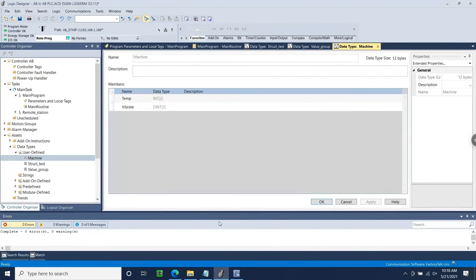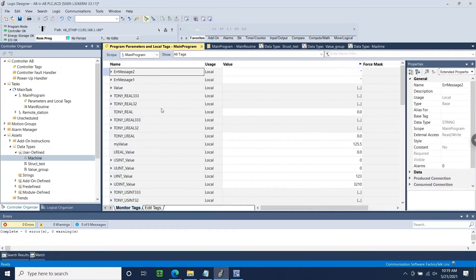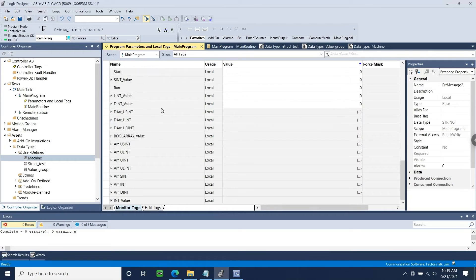Next, let's open our Compact Logix project in Studio 5000 and export our tag list. There are two different file formats that are supported within EasyBuilder Pro: CSV and L5X. When possible, our support team recommends using an L5X file during tag import. The L5X file will contain information pertaining to UDTs, remote IO, and alias tags configured within Studio 5000.